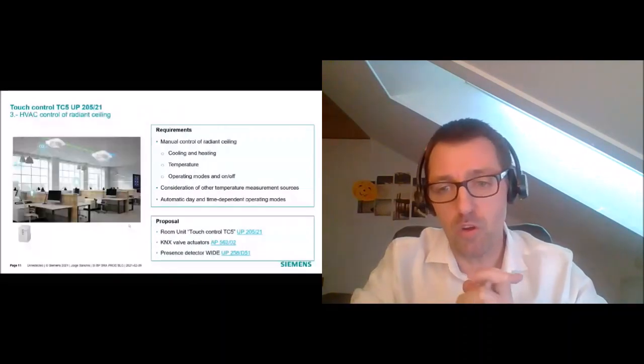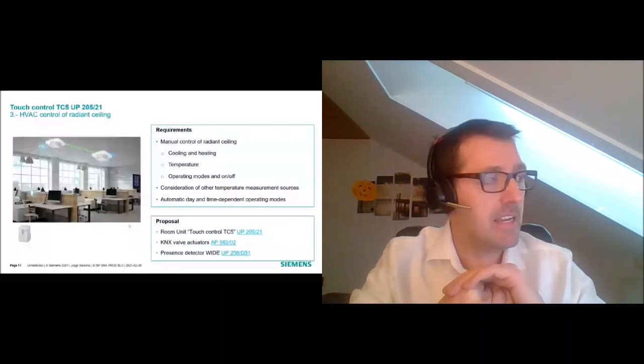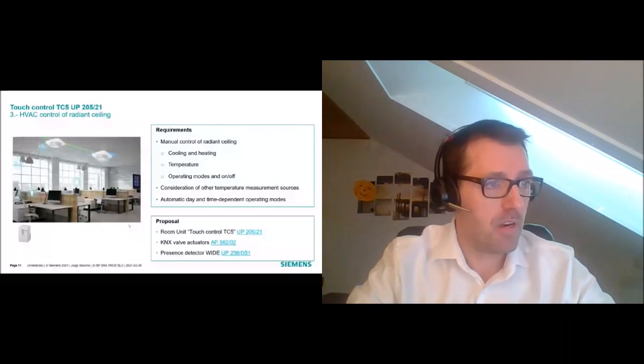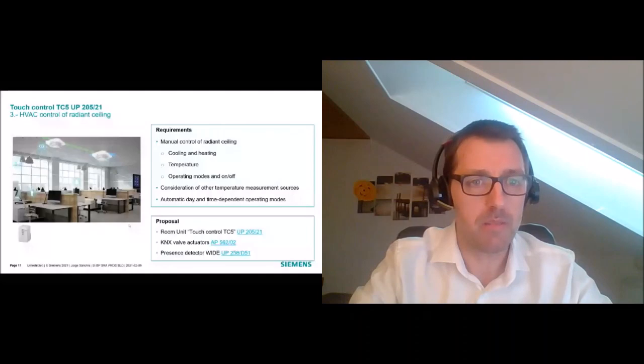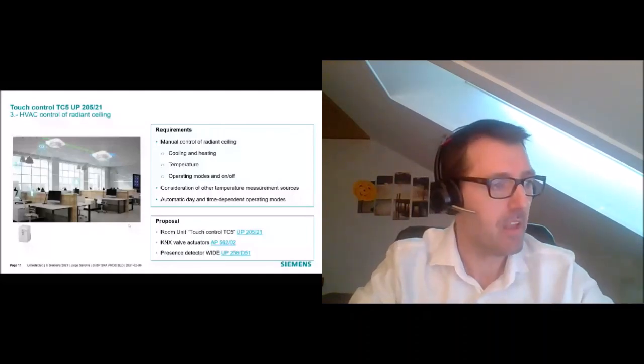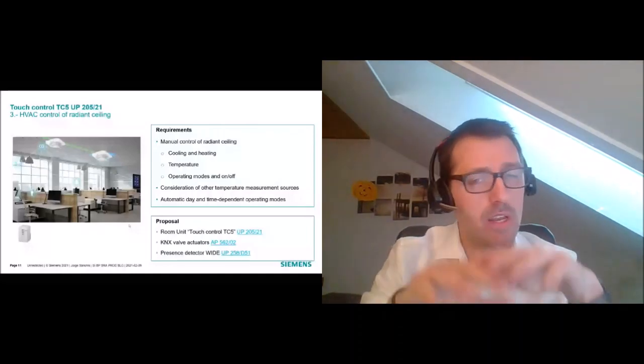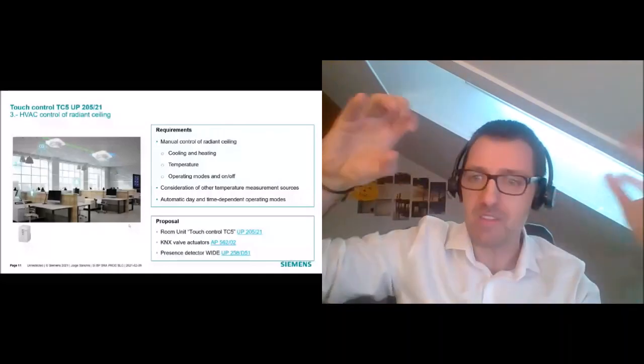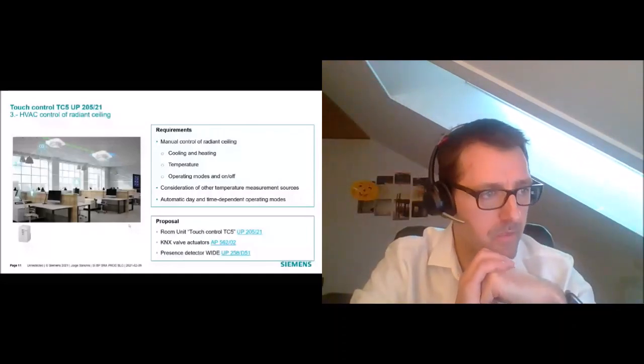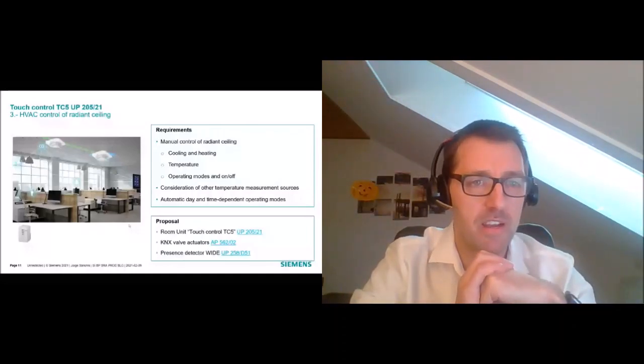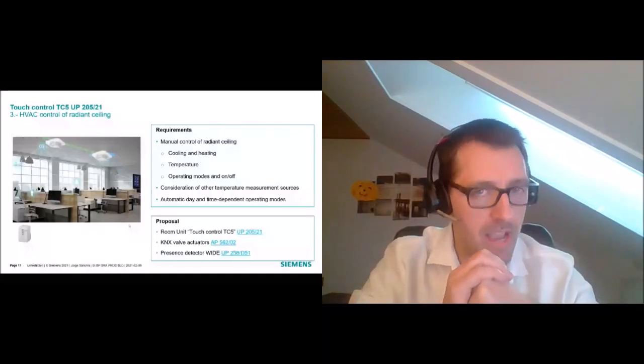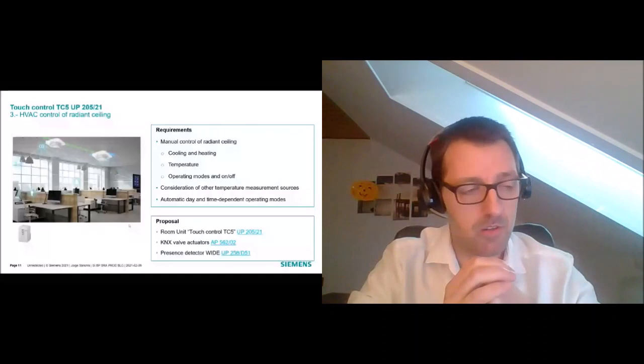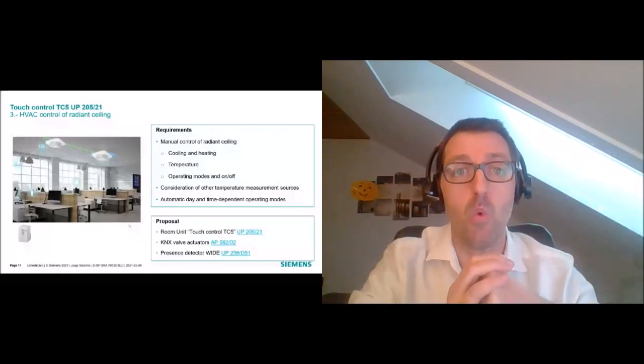Use Case 1: HVAC control of a radiant ceiling — just an example, it could be floor heating or a radiator. The customer is asking for setpoint control, cooling, heating, temperature operating modes, and on/off. Additionally, we're talking about an open space, so the customer doesn't want to measure temperature only from one wall sensor — we need more inputs around the room. The customer also wants an automatic function to switch on and off the thermostats. The proposal: TC5, KNX valve actuators, and a presence detector — as an example.